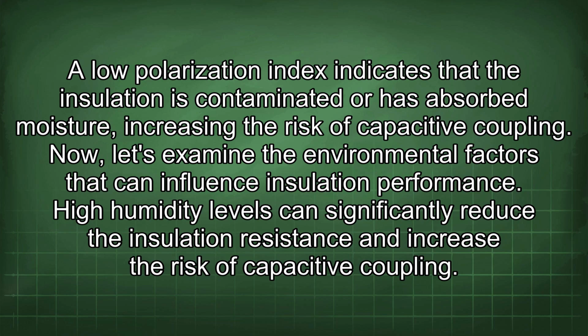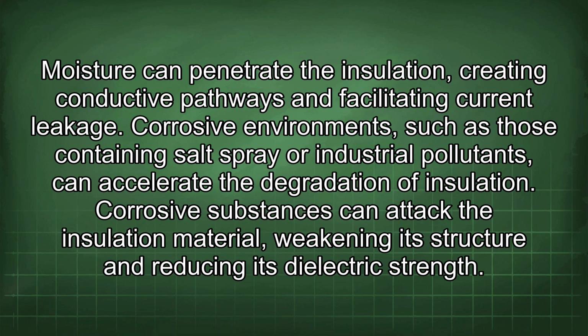Now, let's examine the environmental factors that can influence insulation performance. High humidity levels can significantly reduce the insulation resistance and increase the risk of capacitive coupling. Moisture can penetrate the insulation, creating conductive pathways and facilitating current leakage. Corrosive environments, such as those containing salt spray or industrial pollutants, can accelerate the degradation of insulation. Corrosive substances can attack the insulation material, weakening its structure and reducing its dielectric strength.